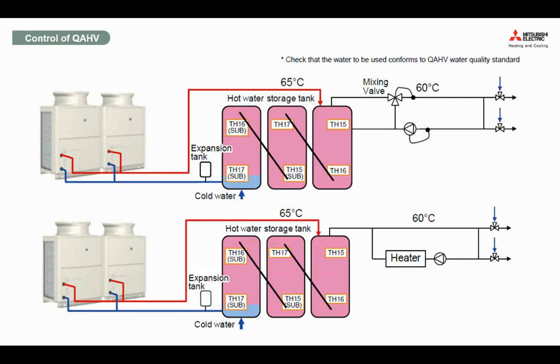And then you have a recirculation pump just to recirculate the water because the load may be low. The hot water demand may be low inside the building. So due to stratification and low hot water demand, you are able to maintain your TH15 on the hot water side on the main unit. So you don't really need a secondary heater, because your recirculation water from your building may be able to dump into the tank. Let's say 60 degrees C of water leaves the tank, and after it travels through your building, maybe it becomes 58, 59 degrees C. Then you dump it into the tank, mixing with 65 degrees C of water, and maybe it will be able to maintain that 60 degrees C into your domestic hot water usage.